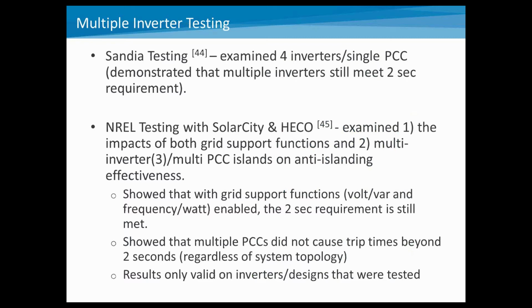If we go on to additional things, one of the questions that often comes up is, what about multiple inverters? Obviously, it's getting rarer now that you see singular DG installations, so we're starting to see much more multiples of inverters. So both Sandia and NREL have done a variety of tests in this space. So Sandia, if you see the reference there, examined 4 inverters at a single point of common coupling and demonstrated that multiple inverters still met the 2-second requirement that's in the standard.